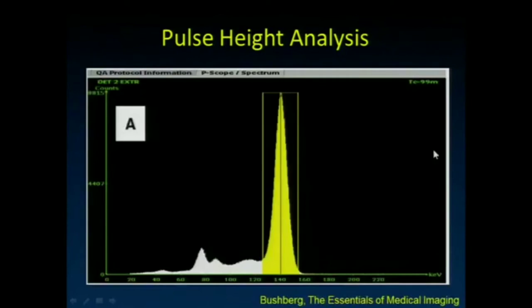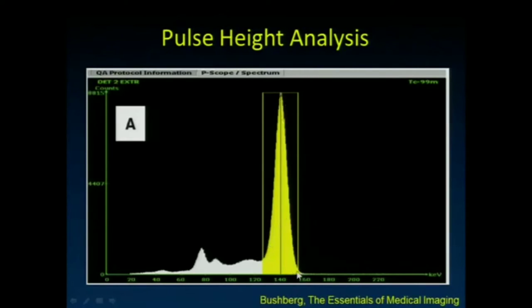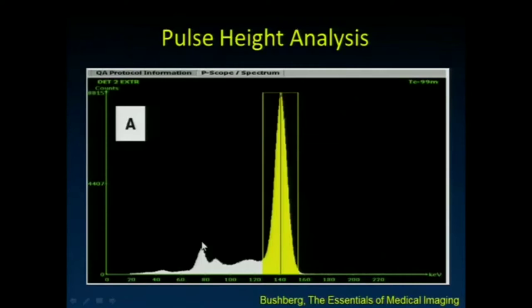When detecting gamma rays from a patient given technetium-99m, we see a big peak centered at 140 keV. The events within our acceptance window are marked as true events used to make the image. Beneath that, there are some scattered events at lower energies. There's a small peak just below 80 keV — anyone know what that peak is from?